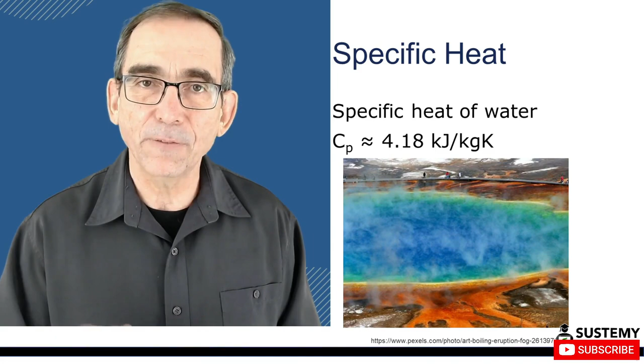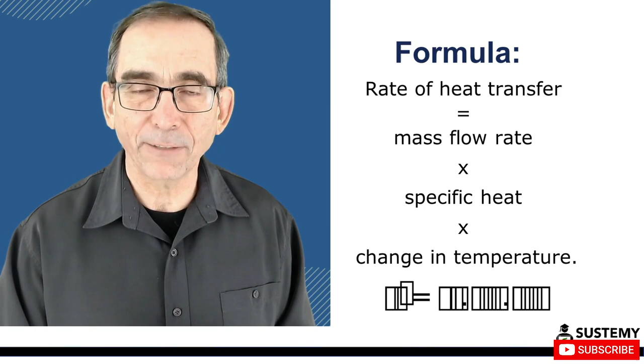Consider, for example, water with a flow rate of 7.2 meters cubed per hour being cooled from 12 degrees to 7 degrees by a chiller. What is the chiller useful output power? Knowing the density and specific heat of water, the amount of cooling energy provided by the chiller can be calculated by using the formula rate of heat transfer equals the mass flow rate times the specific heat, or CP, times the change in temperature. The calculation steps are shown in this table.